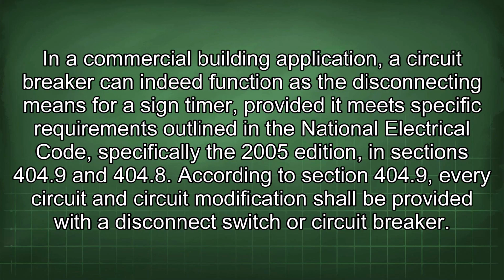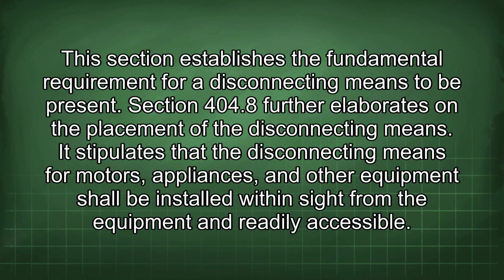In a commercial building application, a circuit breaker can indeed function as the disconnecting means for a sign timer, provided it meets specific requirements outlined in the National Electrical Code, specifically the 2005 edition in sections 404.9 and 404.8. According to section 404.9, every circuit and circuit modification shall be provided with a disconnect switch or circuit breaker. This section establishes the fundamental requirement for a disconnecting means to be present.